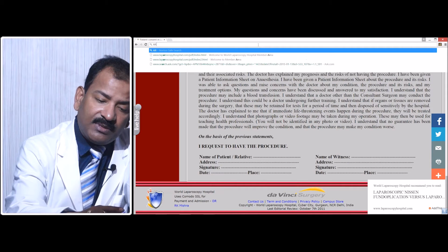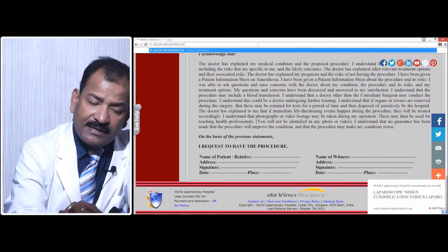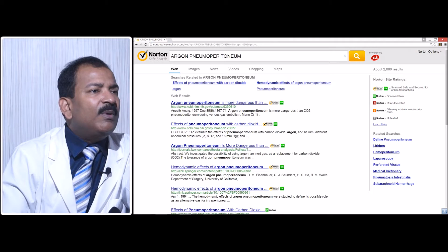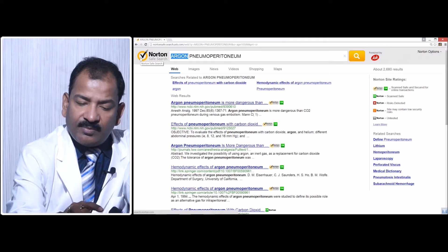So, these are the alternative gases like helium and nitrous oxide. Some people use xenon, some people use argon. If you search the net for xenon pneumoperitoneum or argon pneumoperitoneum, you will find many centers have used these gases, but ultimately we have better results with CO2. Argon has a problem: it is an ionizable gas. So, if you are using electrosurgery, it can transfer electrons from the tissue to the electrode and act as a bridge. Some people are happy using argon, but it does not have benefit over CO2. Then xenon is also used by many people.